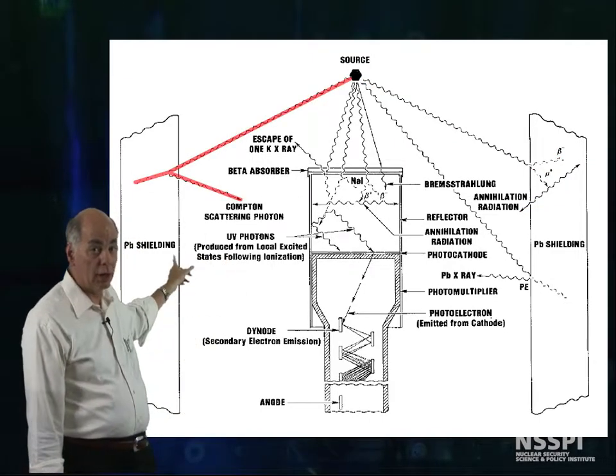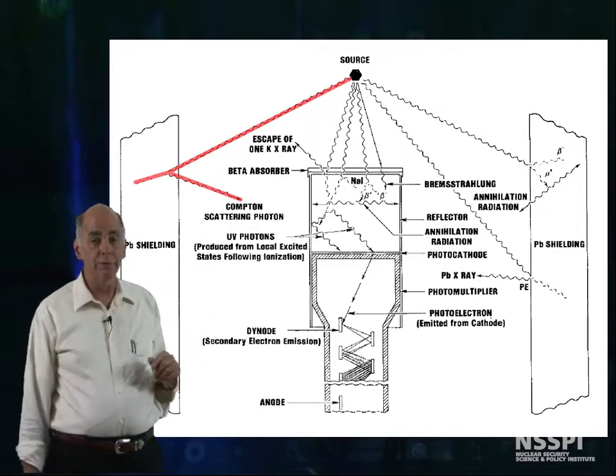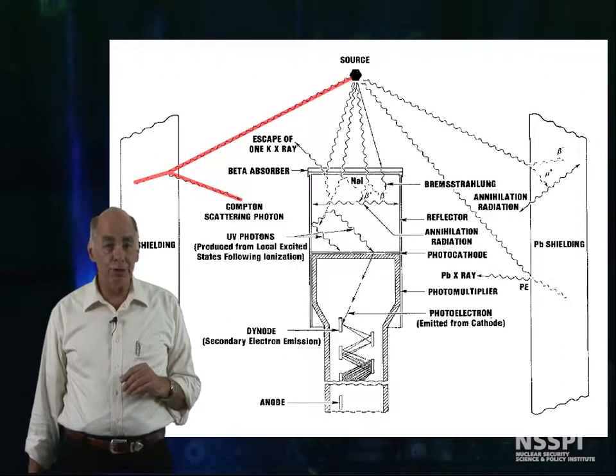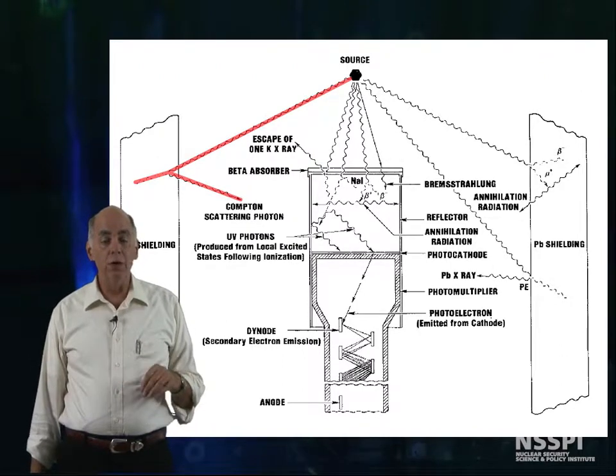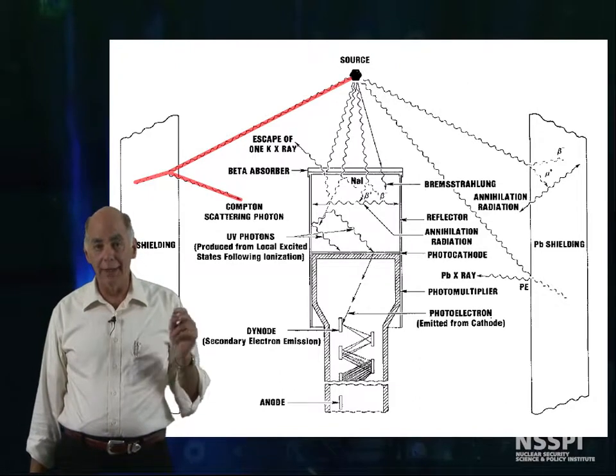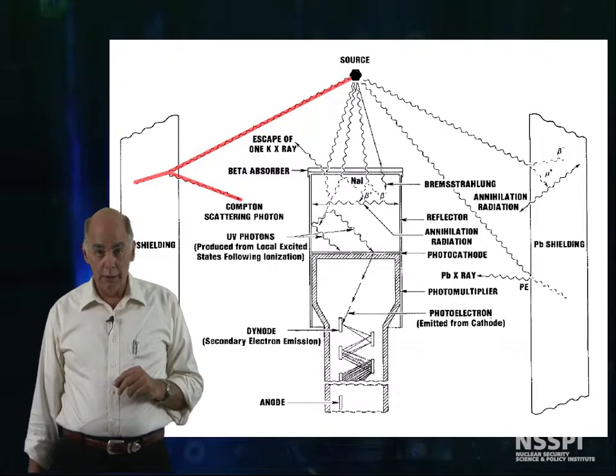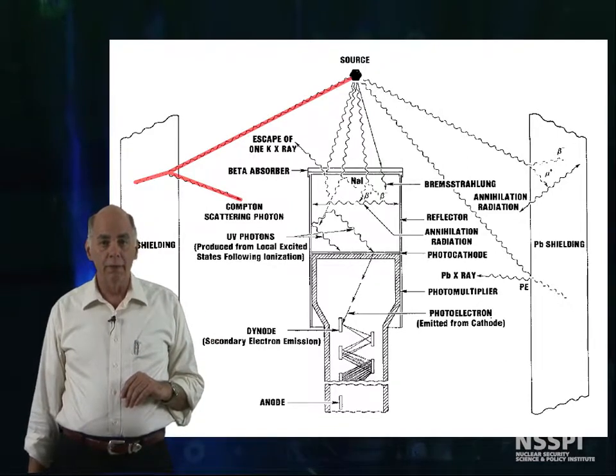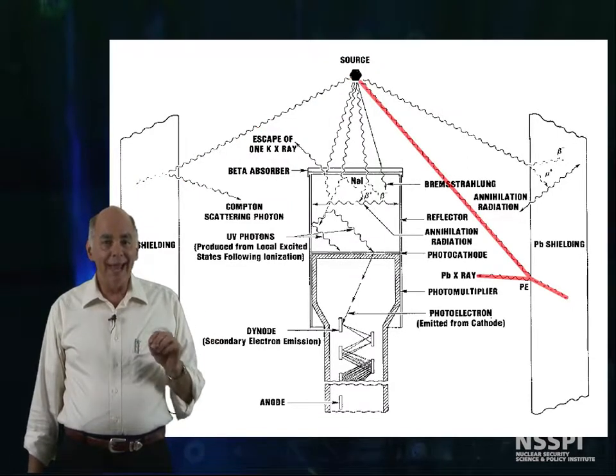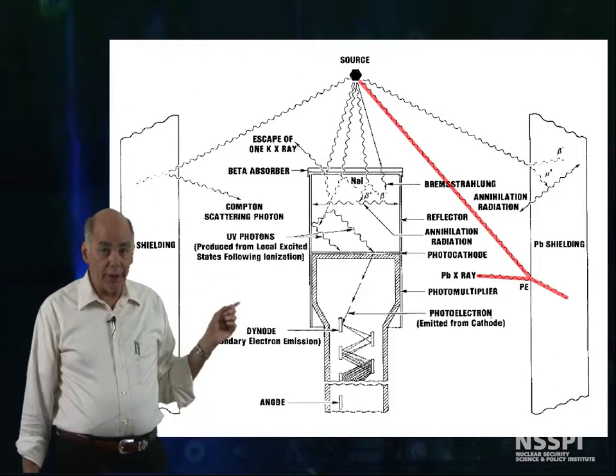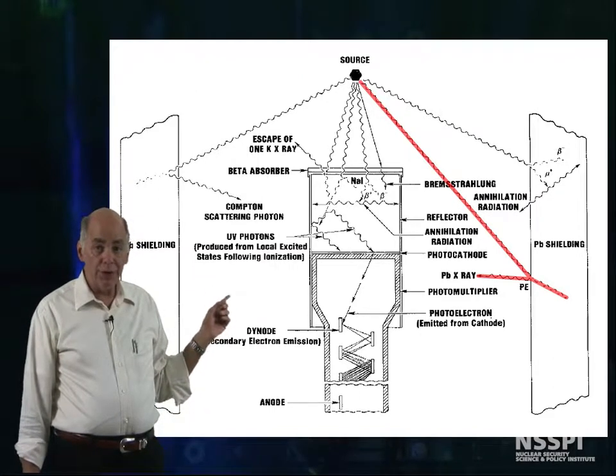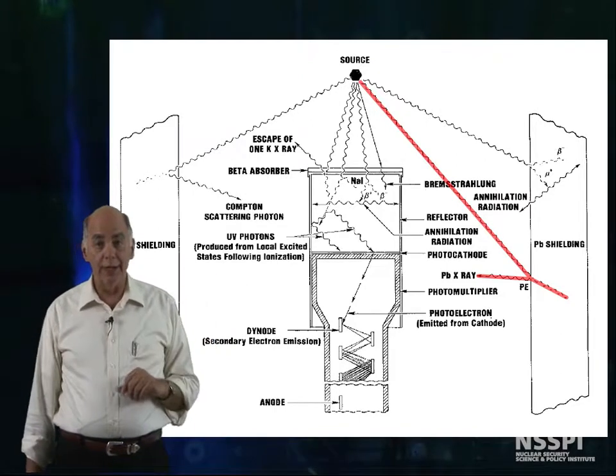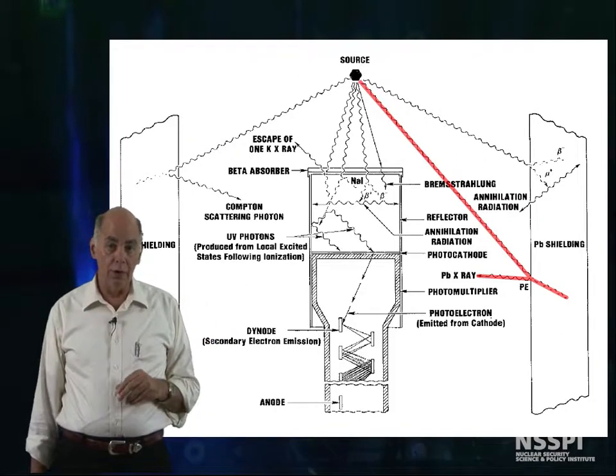As shown here, a gamma from the source can suffer a Compton interaction in the shielding, and the resulting Compton photon can be counted. And, as before, this is not part of the original spectrum. With any gamma interacting in the shielding, lead characteristic x-rays will be produced. These can also enter the detector, and again, they're not part of the source spectrum.